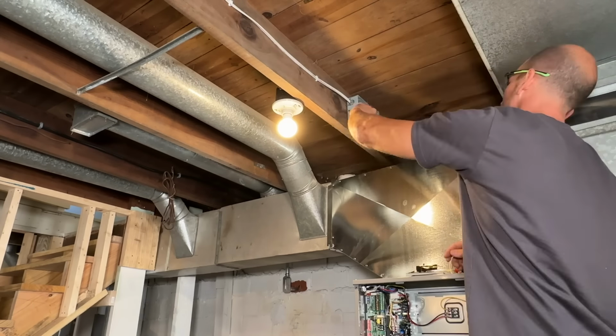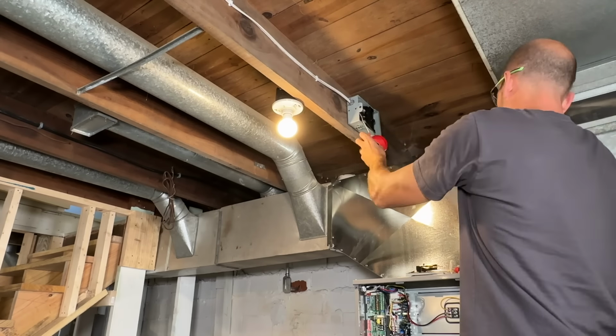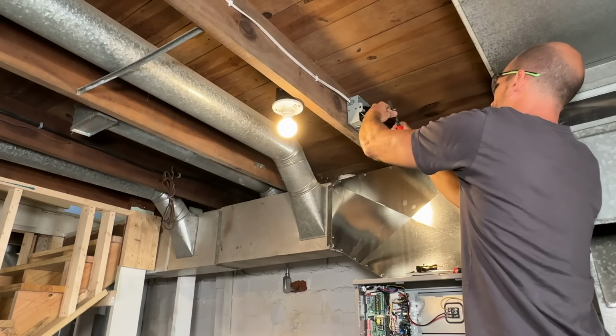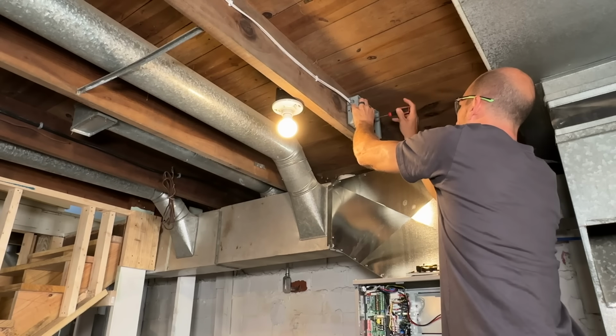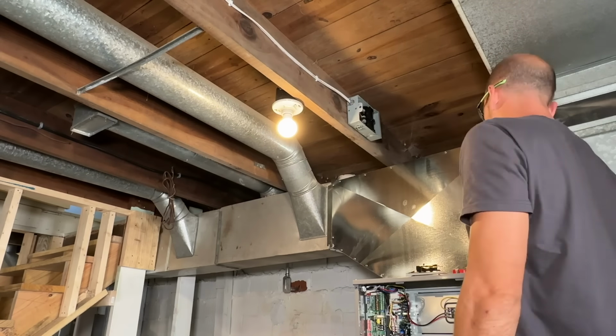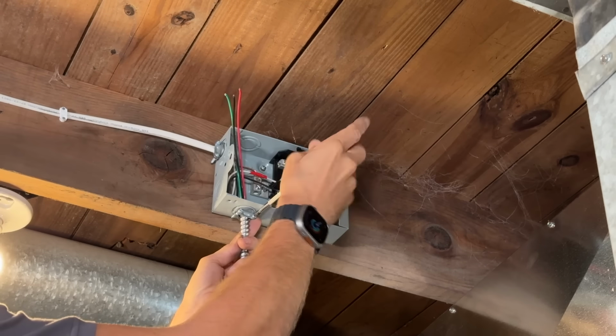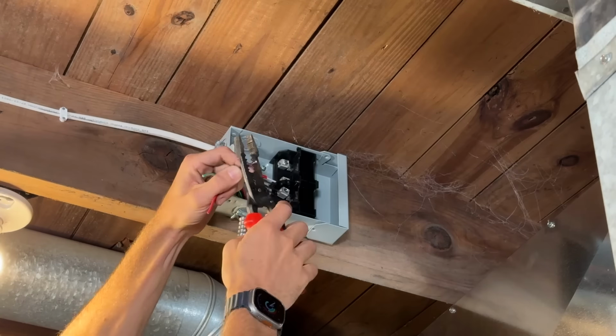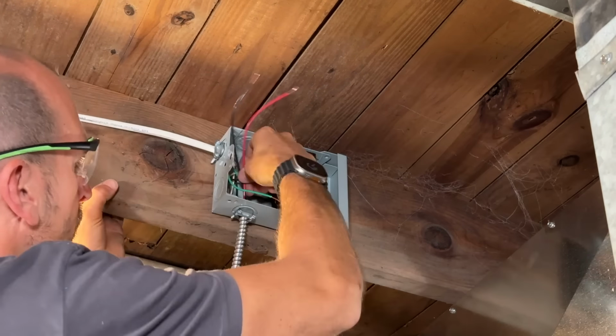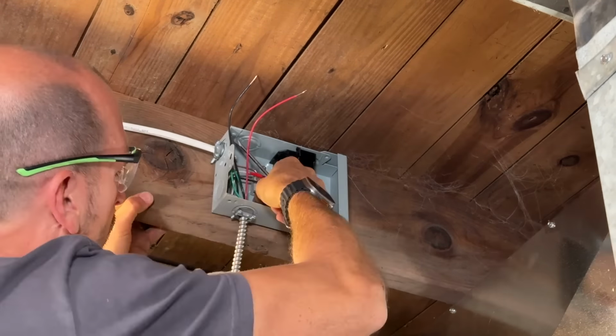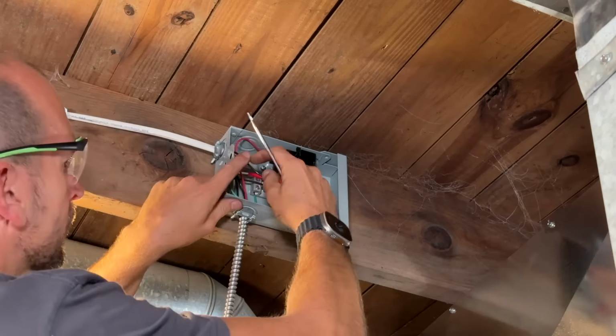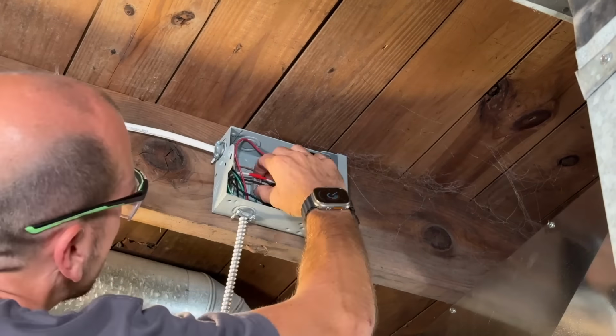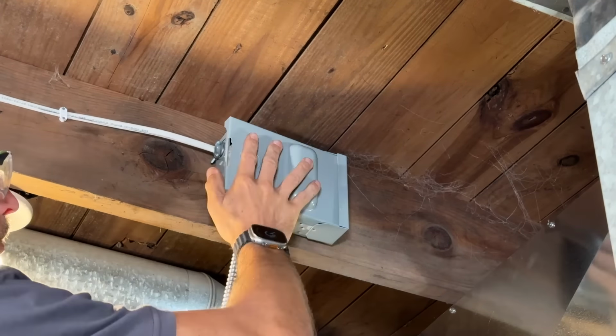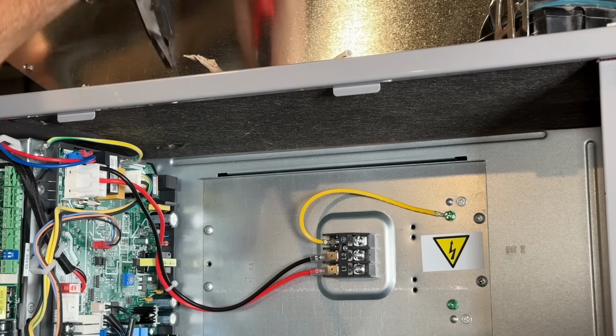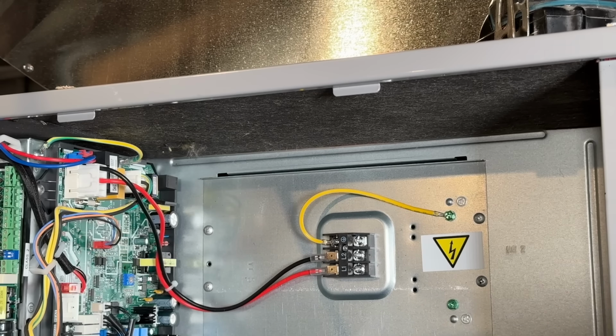So similar to the outdoor unit, we're connecting up our 2 conductors, and I am marking the white conductor with red tape. This was noted by some of the viewers in my last video, and that was, hey, if you're going to use white conductor, which is usually neutral, you need to mark that because it's now a hot conductor, and that could be confusing to future people servicing the actual unit.